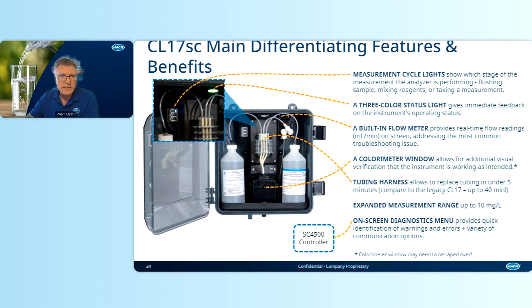The 3-color status light is visible from far away and tells the operator immediately the analyzer is doing well with the green light, or it requires some attention with the yellow, or it's not working and requires immediate attention with the amber or red light. The built-in flow meter provides real-time flow readings. However, it has other functions, such as automatic standby and automatic restart of the analyzer. So there are multiple features and functions, even though the built-in flow meter is an optional device.